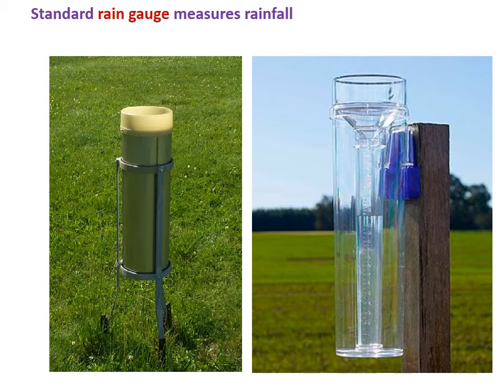This measuring cylinder is not the usual one, but it is marked in millimeters and not milliliters, so that you can easily know how much rain fell for a particular period of time, say the last 24 hours. This can be read by taking out the funnel as well as the jar from this device, and then directly reading the amount of rainfall.